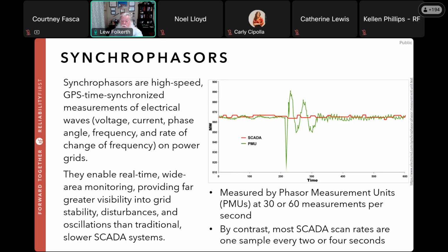Now, this creates a challenge because that's a lot of data. So you have to get that data from the phasor measurement unit, or PMU, usually through a phasor data concentrator, or PDC, back to the system that's going to be using it. So this provides wide area monitoring, depending on where your phasor measurement units are installed. But typically, you've got a wide area monitoring effect because you have a lot of these PMUs scattered around. At last count I saw, I think there were 700 and some. Let's go to the next slide, please.